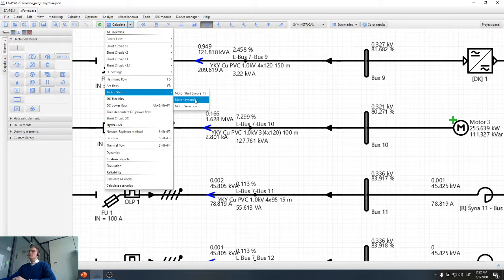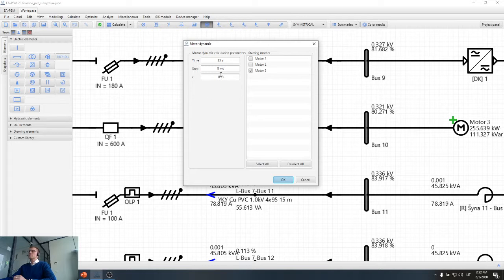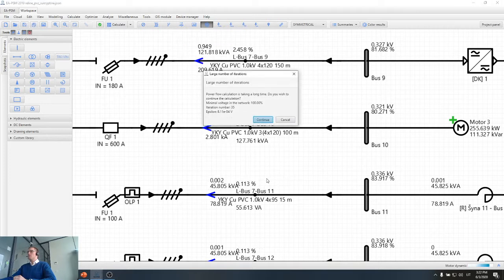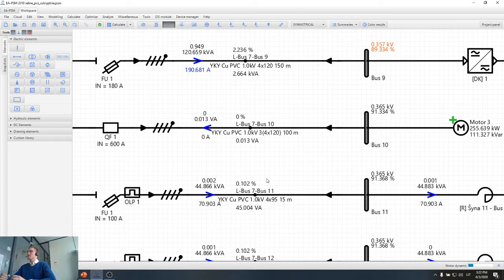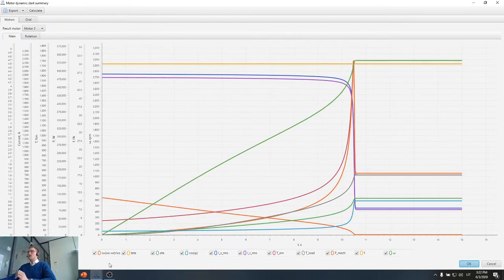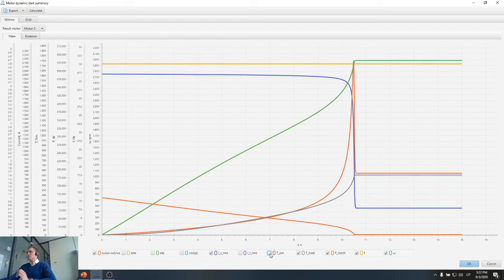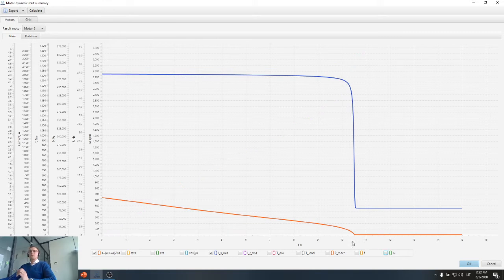However, for more detailed analysis, we can also use motor dynamic functionality. In our software, we have this feature which allows us to calculate motor starting. Let's try this functionality. I will set the step time and calculation period time to estimate the motor starting current and motor starting time. As I have mentioned, while simple motor starting gives more conservative results, this motor starting gives more accurate and in most cases less conservative results. For example, here we can see that the motor starting current is about 2000 amps. Here is the stator current, this blue one. And the motor starting time is around 10.5 seconds.